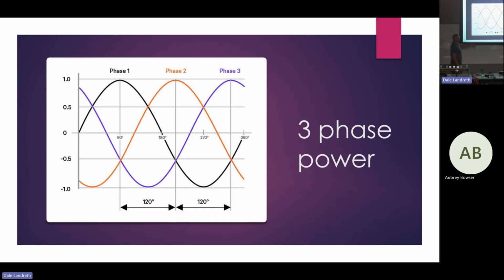So those shading rings produce another magnetic field that is not, I think it's 90 degrees out from the sine wave or whatever - so it's like you see here, these are 120, that shading would be, I think, like 90 if I'm correct. Don't hold me to that, but I'm pretty sure that's what it was. So when that voltage or that sine wave gets to where there's no magnetic field, that shading ring produces or has a magnetic field.